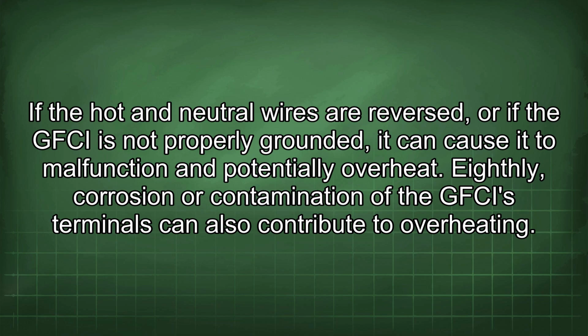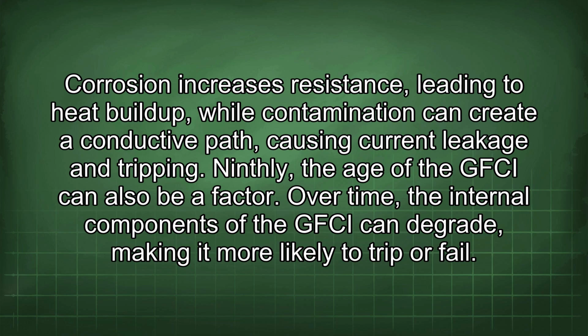Eighthly, corrosion or contamination of the GFCI's terminals can also contribute to overheating. Corrosion increases resistance, leading to heat buildup, while contamination can create a conductive path, causing current leakage and tripping. Ninthly, the age of the GFCI can also be a factor. Over time, the internal components of the GFCI can degrade, making it more likely to trip or fail.